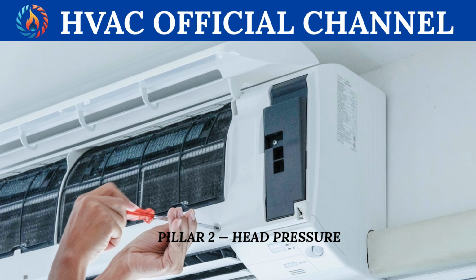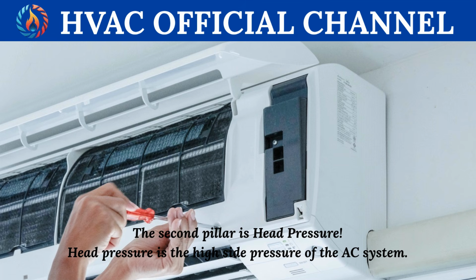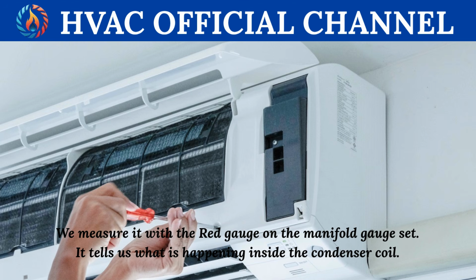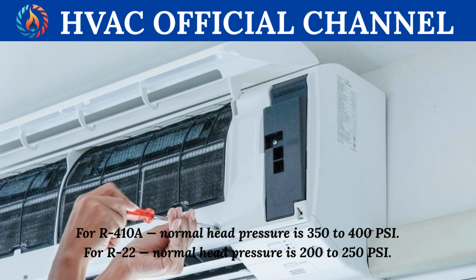Pillar 2. Head pressure. The second pillar is head pressure. Head pressure is the high side pressure of the AC system. We measure it with the red gauge on the manifold gauge set. It tells us what is happening inside the condenser coil. For R410A, normal head pressure is 350 to 400 psi. For R22, normal head pressure is 200 to 250 psi.